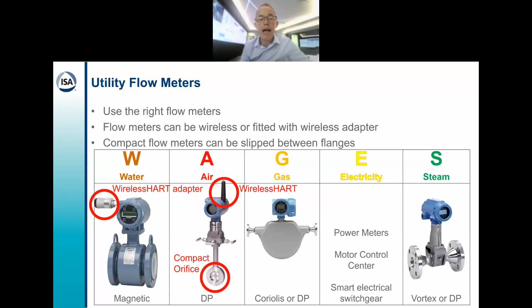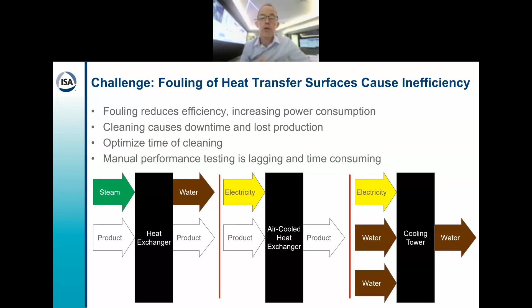Another plant challenge is that fouled equipment like heat exchangers, cooling towers, and air-cooled heat exchangers have lower efficiency, increasing energy consumption. But cleaning to restore performance is disruptive and costly. So the trick is to optimize the timing of the cleaning based on performance analytics. Now, manual performance monitoring has limitations in that it's time consuming and not real time. So the recommendation is to automate equipment performance analytics.